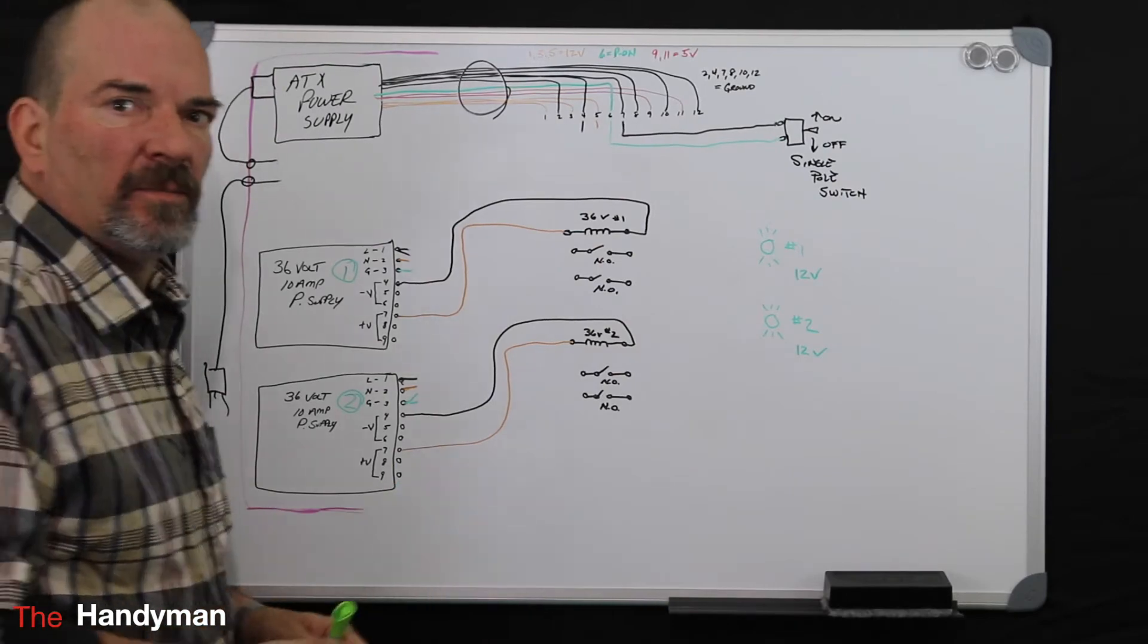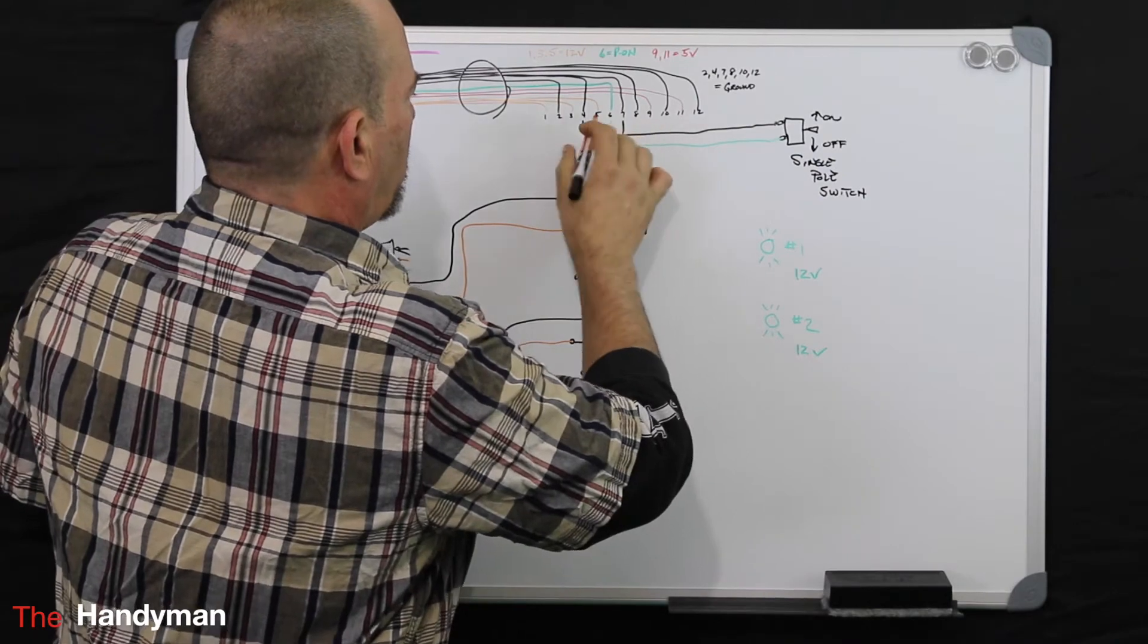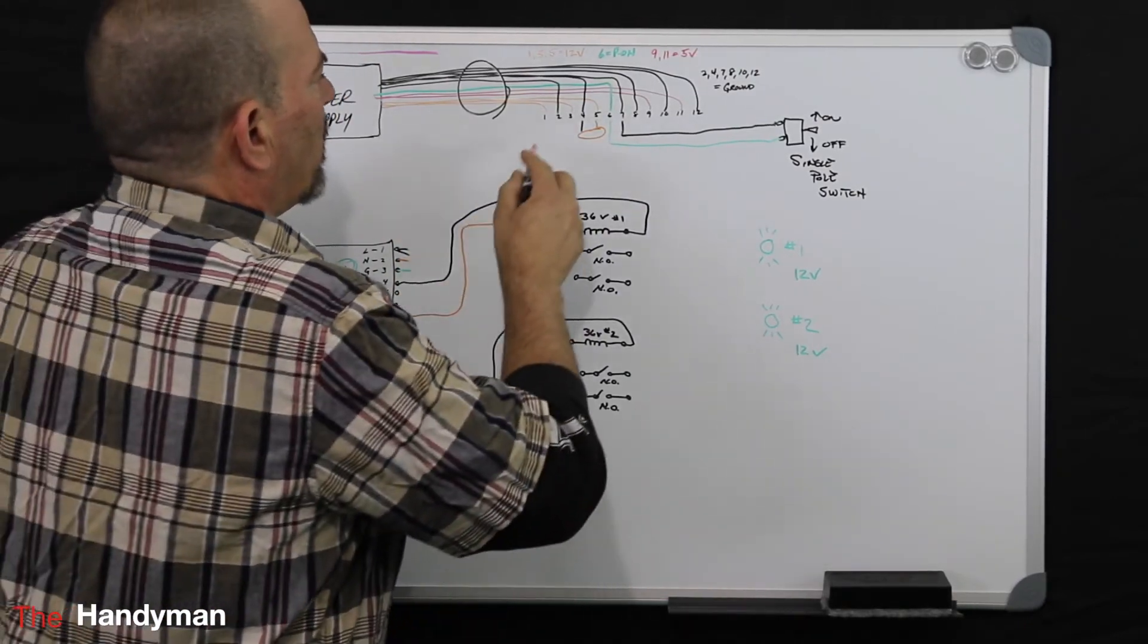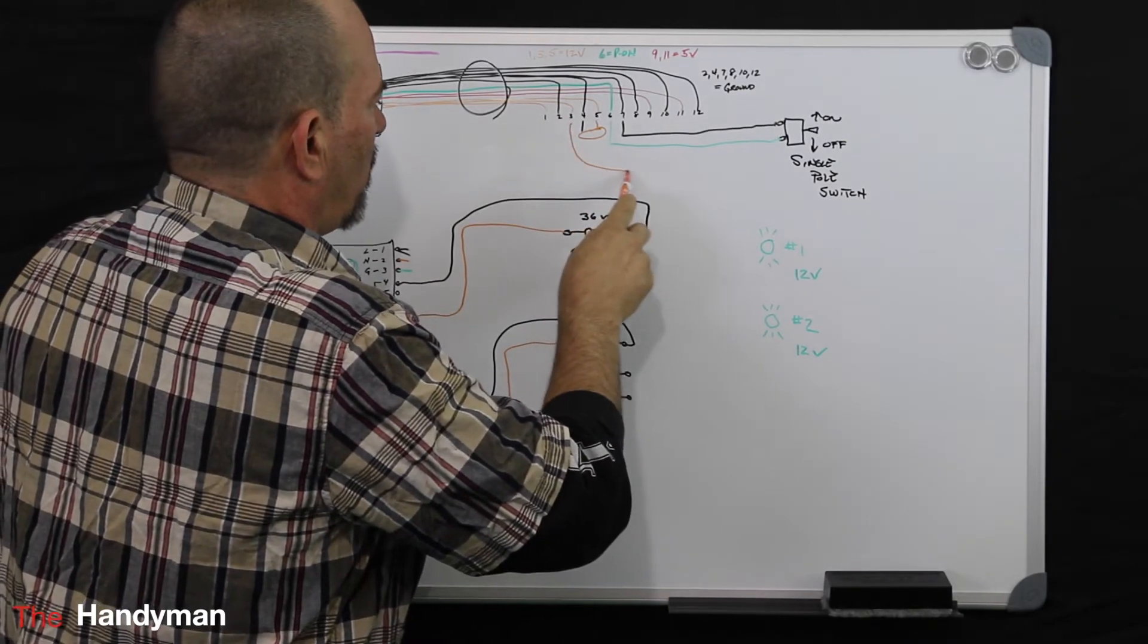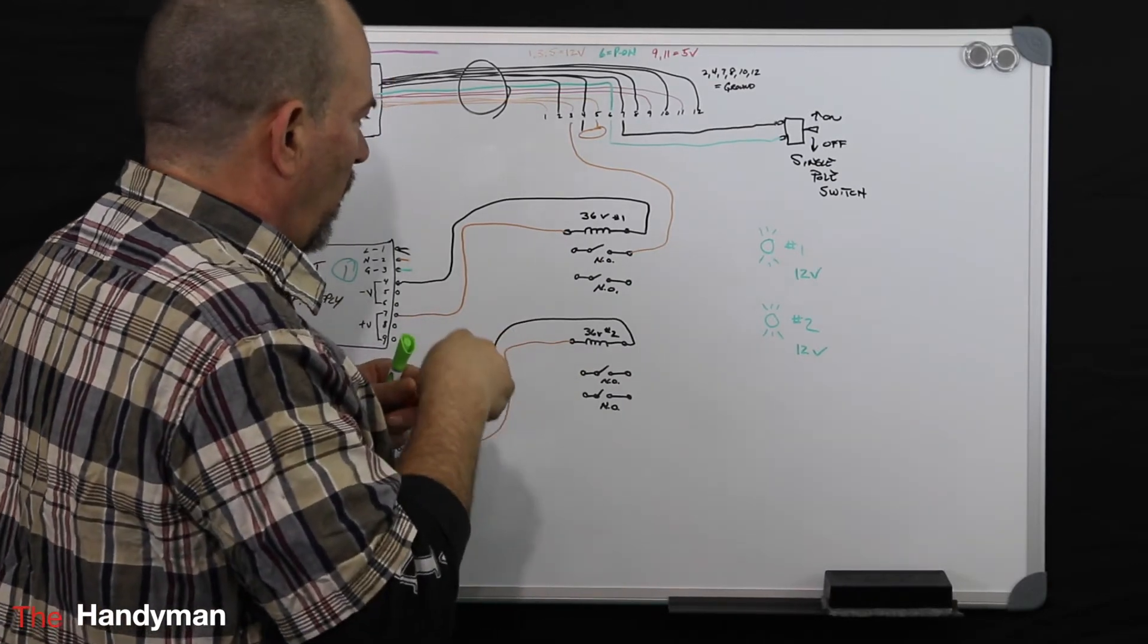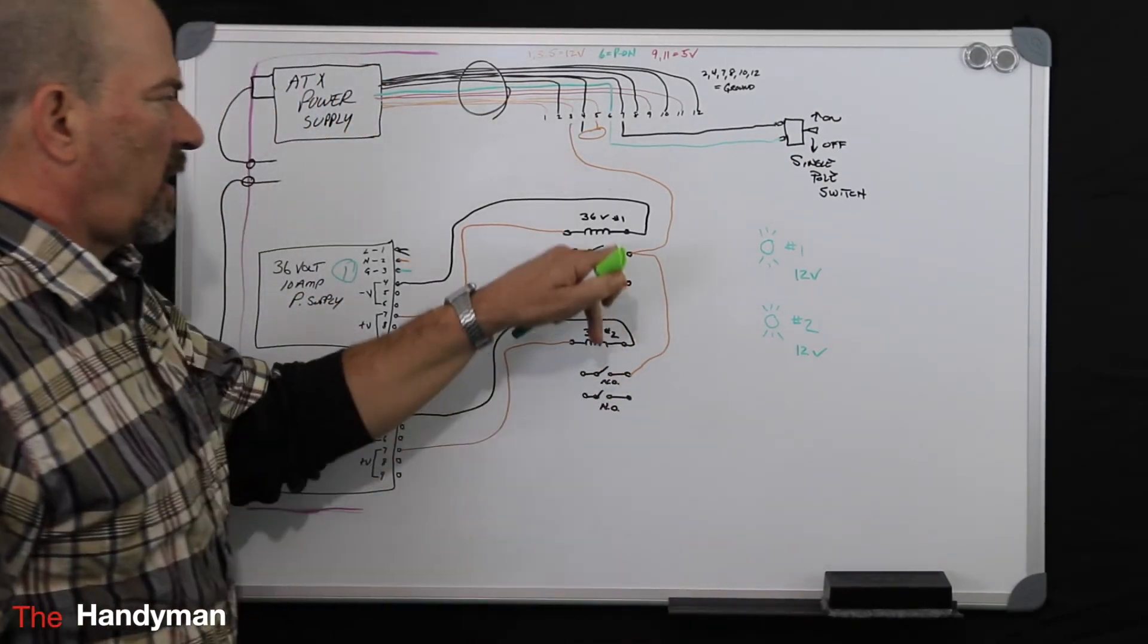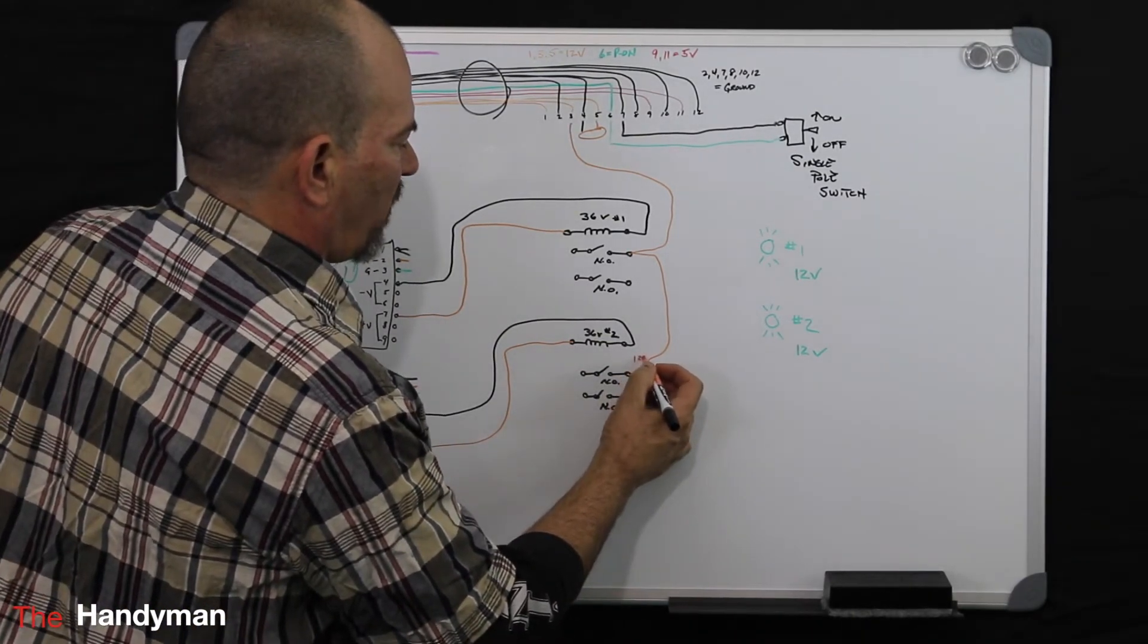So what you need to do here is you need to take your 12 volts. We've already used points 4 and 5 up here, so we're going to take 12 volts off number 3. And you can jumper these and put them to one side of your normally open contacts. So this is your 12 volts supplying one side.